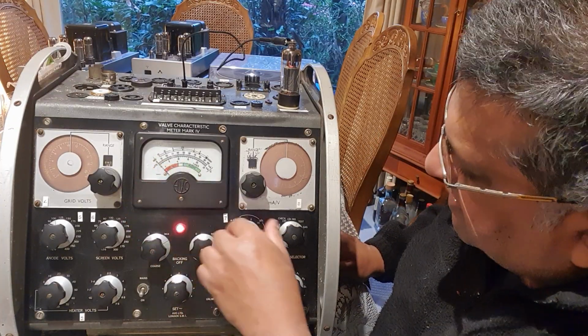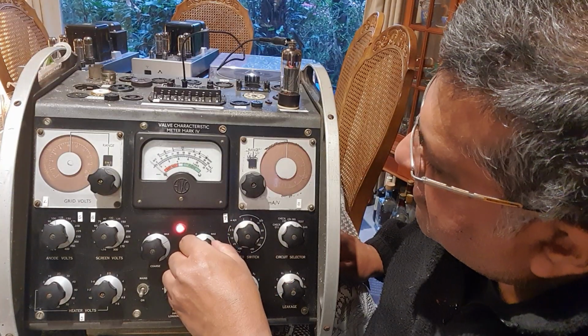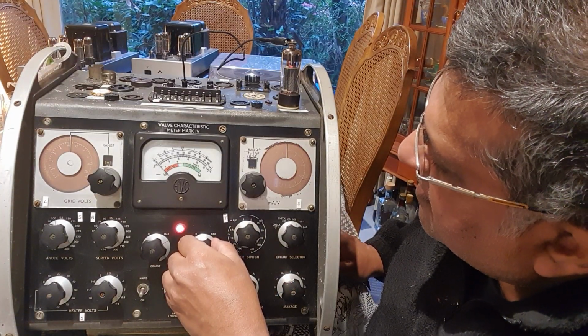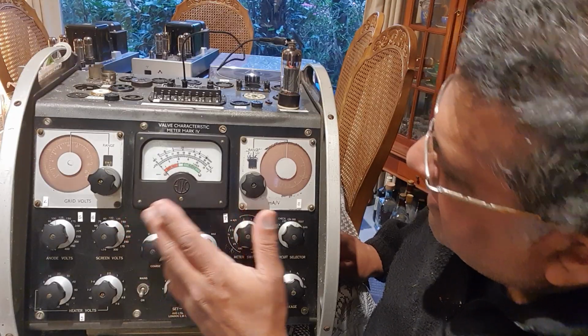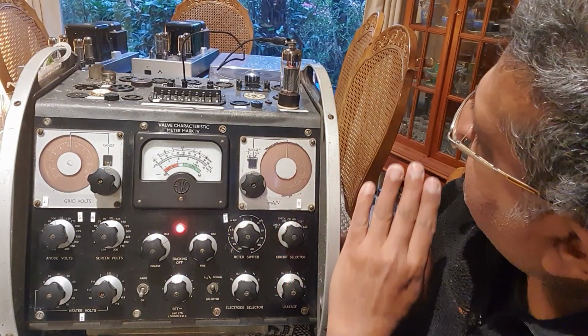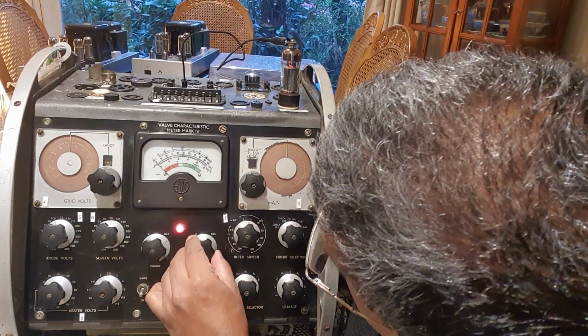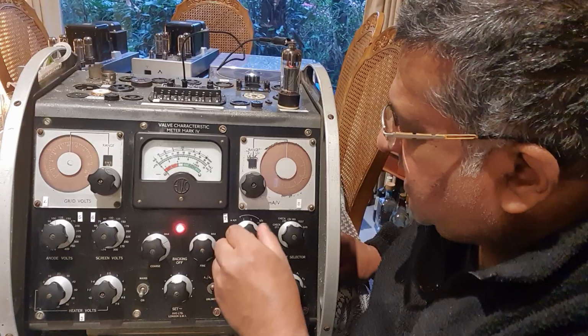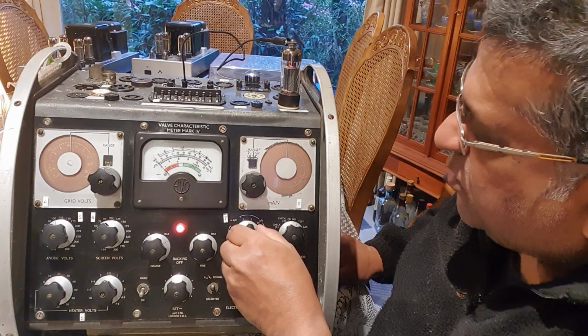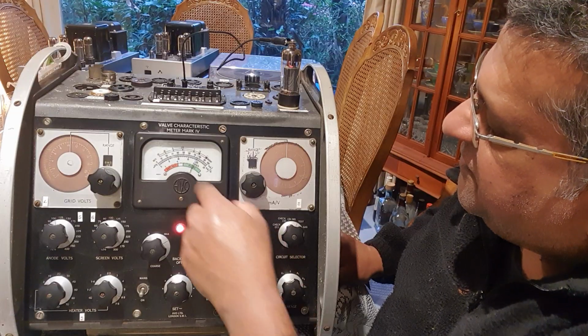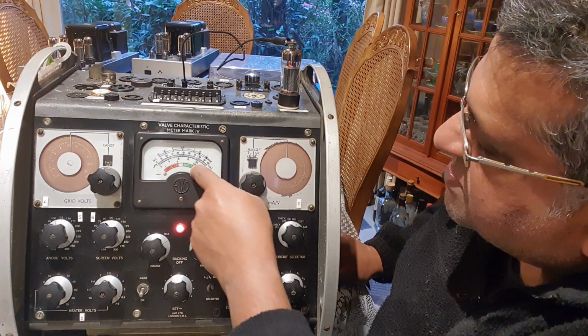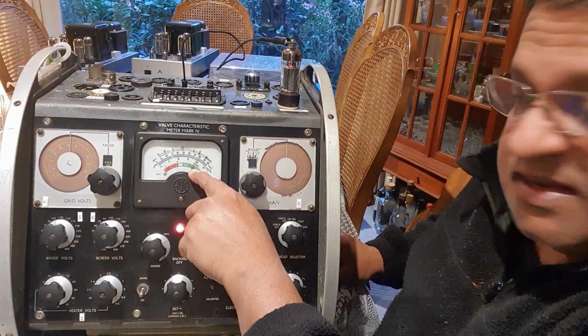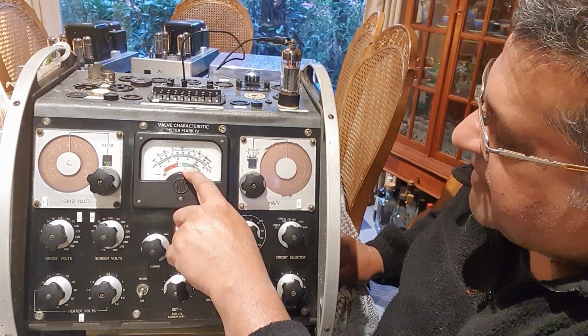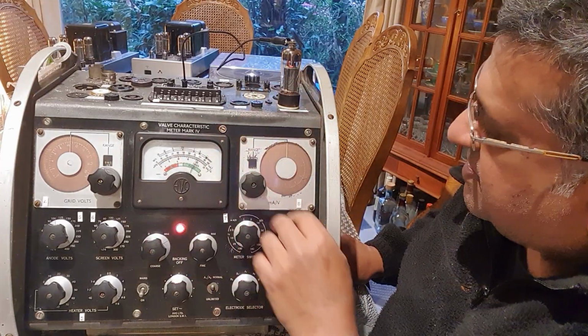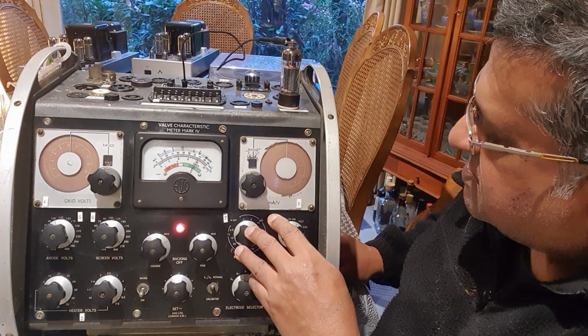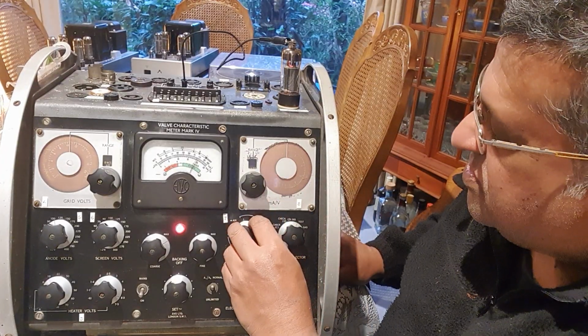Bring it to 0. We're trying to bring the meter to 0. Don't go straight to 25, 2.5. So that's 0. Now the meter is at 0. We've added an extra volt. There, it's slowly deflecting, and we are now going to add that 1 volt and see if that meter needle goes up to the good mark. And there's a mark here, a green line that says good, and it has deflected there. So that means the meter is working and the valve is very good. It's 100%. There's no dramas.